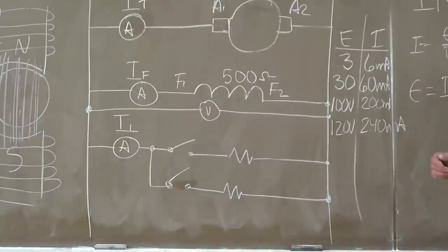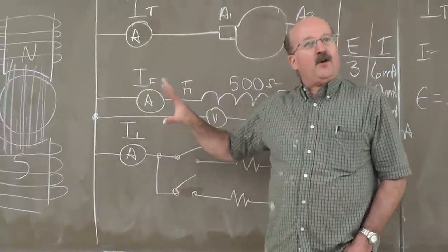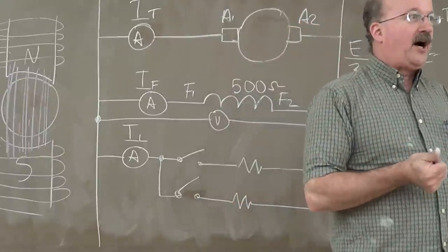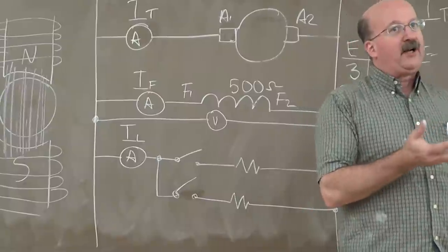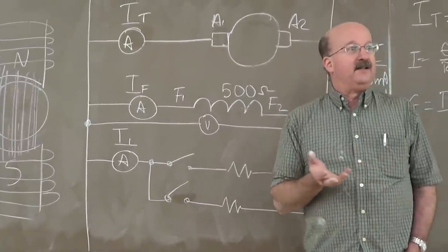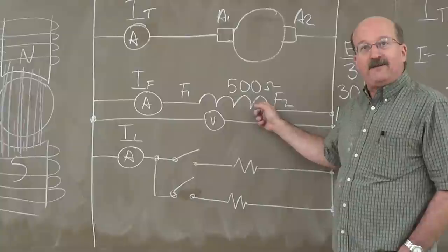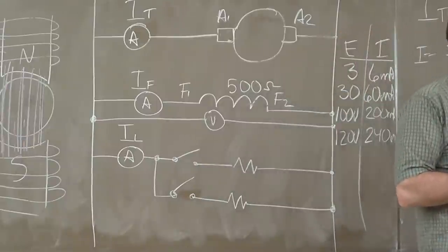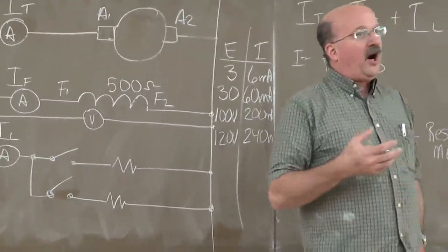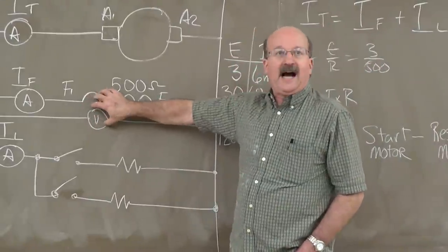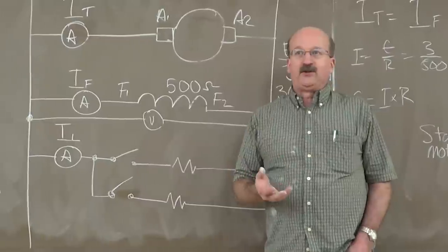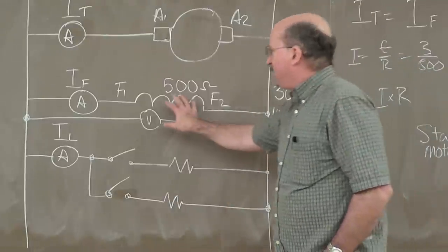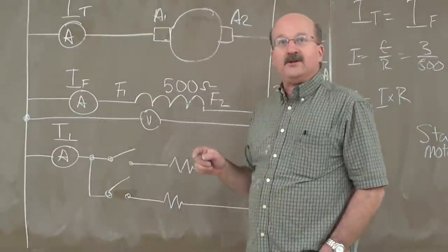One of the things is that you don't need to know how to design these generators, but you do need to know how they operate so you can troubleshoot them. If your generator's not working, how is it connected? Is it connected as a self-excited generator, or is it a separately excited generator, or a series generator? All of these things will dictate how this generator operates, and as far as troubleshooting, will weigh into what you're doing. You may have this connected up with the field connected up backwards.